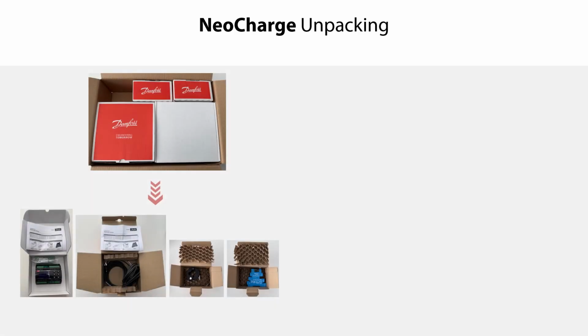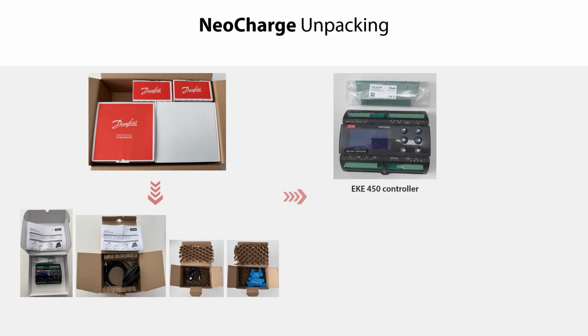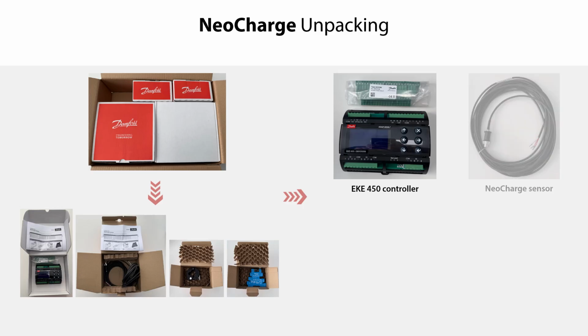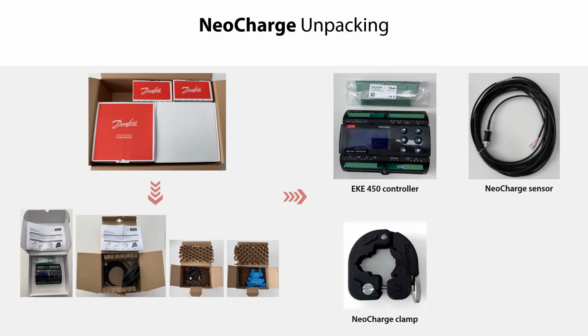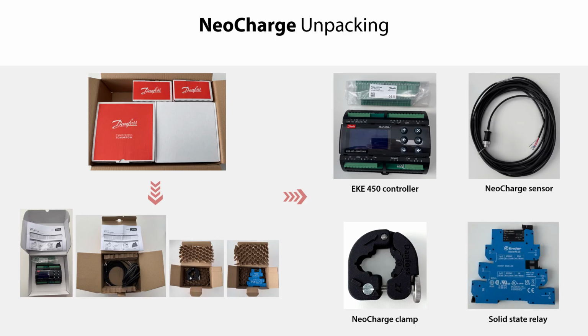Here you see what is included in the box with the Neocharge when you unpack it. As seen here, the box includes an EKE 450 controller, a Neocharge sensor, a sensor clamp and a clamp insert to adjust the clamp to different evaporator tube outer diameters. And finally, a solid-state relay. Please note that there is an installation guide included in each of the boxes. So let us get started with the installation.